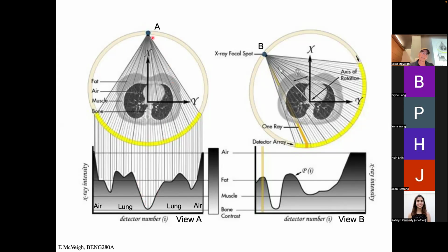If we look over here, the X-ray didn't hit anything. There's nothing in its path. So it's a clean shot to the detector. So you get the maximum number of X-rays in that detector. That's an important number, and we'll measure that number every morning on this scanner. It's just like, if I had air in here, if I took the patient out and just put X-rays through, what would that number be that hits here, right? So we'll see in the math, you need to know that number, actually. So they measure it every day.